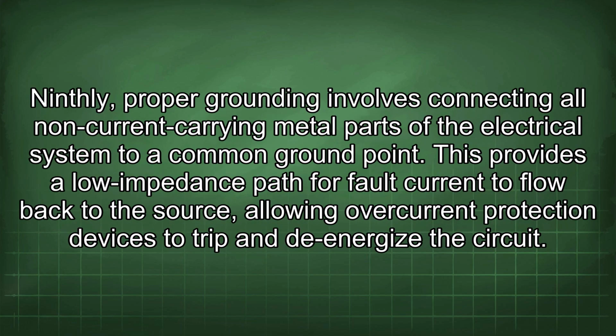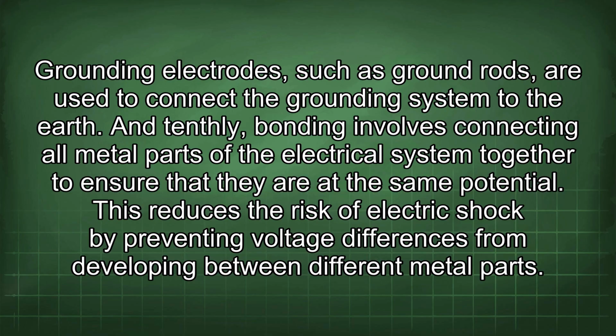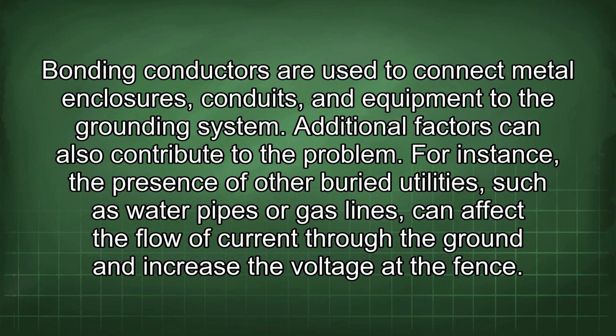Ninthly, proper grounding involves connecting all non-current carrying metal parts of the electrical system to a common ground point. This provides a lower impedance path for fault current to flow back to the source, allowing overcurrent protection devices to trip and de-energize the circuit. Grounding electrodes, such as ground rods, are used to connect the grounding system to the earth. And tenthly, bonding involves connecting all metal parts of the electrical system together to ensure that they are at the same potential. This reduces the risk of electric shock by preventing voltage differences from developing between different metal parts. Bonding conductors are used to connect metal enclosures, conduits, and equipment to the grounding system.